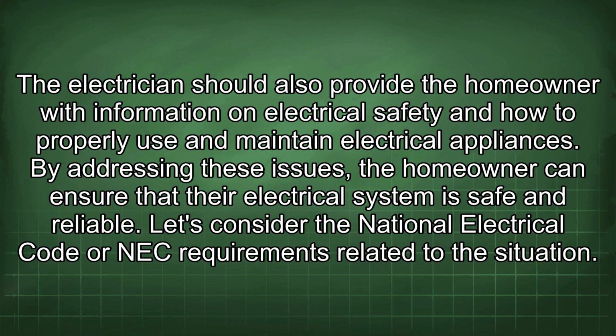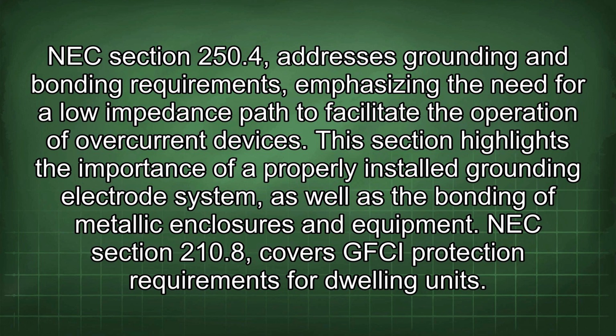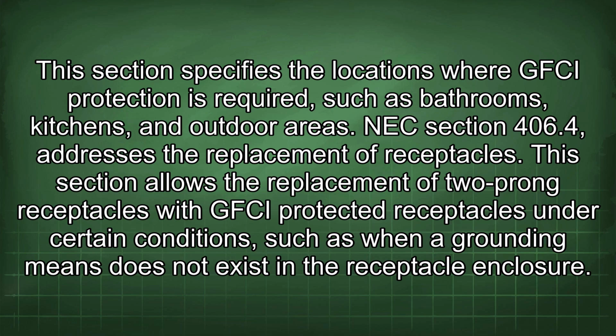Let's consider the National Electrical Code, or NEC, requirements related to the situation. NEC Section 250.4 addresses grounding and bonding requirements, emphasizing the need for a low impedance path to facilitate the operation of overcurrent devices. This section highlights the importance of a properly installed grounding electrode system, as well as the bonding of metallic enclosures and equipment. NEC Section 210.8 covers GFCI protection requirements for dwelling units. This section specifies the locations where GFCI protection is required, such as bathrooms, kitchens, and outdoor areas.